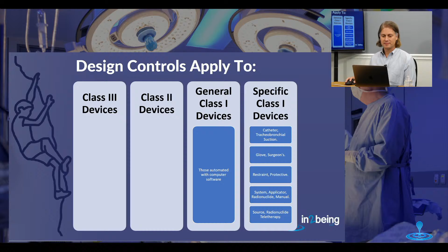Now, we're going to be making some summaries in the upcoming slides. These summaries do not replace going back and reading 820.30. The way that we've summarized it may miss a small nuance. The goal here is to make sure that you understand the overarching points of this design control regulation. So go read 21 CFR 820.30 for more information.